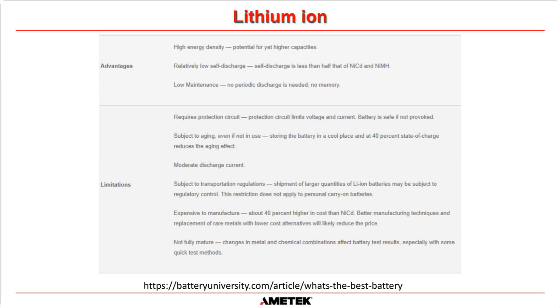The limitations: it requires a protection circuit. The battery is safe if not provoked, it says. Basically, if the battery starts to go into thermal runaway and looks like it's going to go on fire, the only thing that you can do is disconnect that battery from the charging system. And in truth, that does not prevent it from continuing to go into an unsafe mode. But there's a lot of things being done in the new technologies, obviously because of Samsung and everybody else's batteries going on fire. They're much safer than they used to be, but they still have to have protection circuits to make sure that the batteries don't get into a hazardous, fire-creating state. They're also subject to aging, even if not in use.